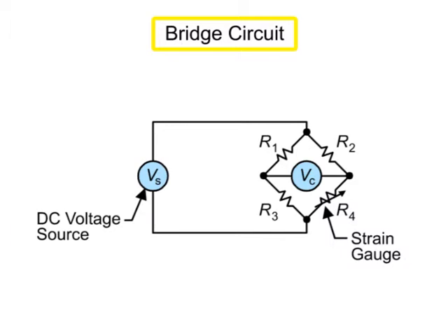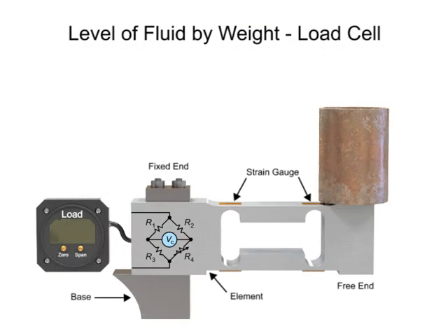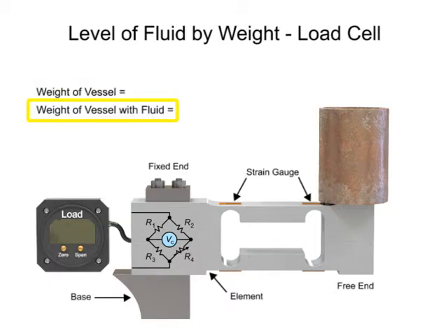Connected to a bridge circuit, the force measured is proportional to the output voltage. The output voltage is converted to a level measurement when vessel weight and vessel fluid density is known.